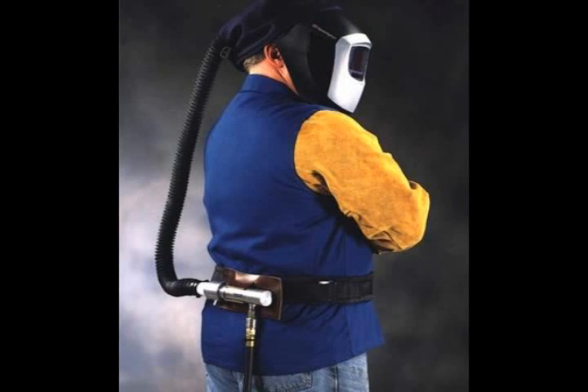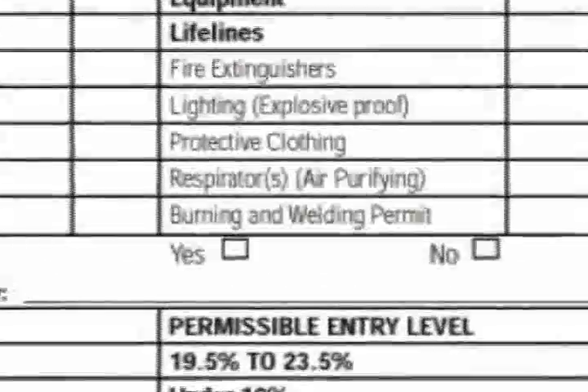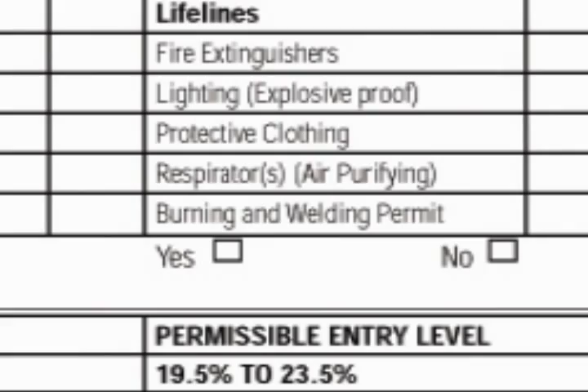In this last scenario, Cliff will be stick welding and then carbon arc cutting in a confined space. Any time you're performing hot work in a confined space, regulations require that you use ventilation. You are likely to need a respirator too. Cliff is wearing a respirator while performing these operations. A permit is required prior to working in a confined space and the air must be tested to see if there is enough oxygen.